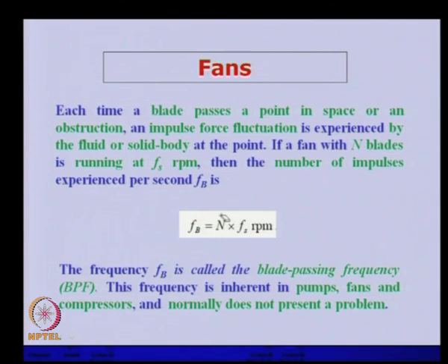This is called the blade passing frequency, BPF, similar to the tooth meshing frequency. This frequency is inherent in pumps, fans and compressors. Normally it does not present a problem, but if there is some fault, then we can have difficulty at this particular frequency.